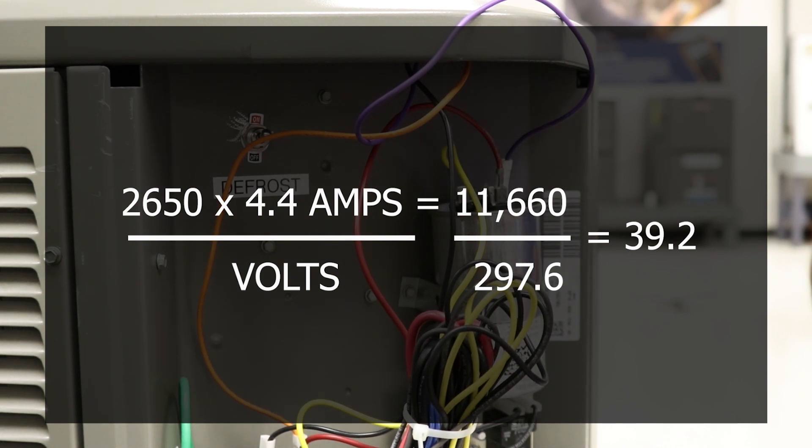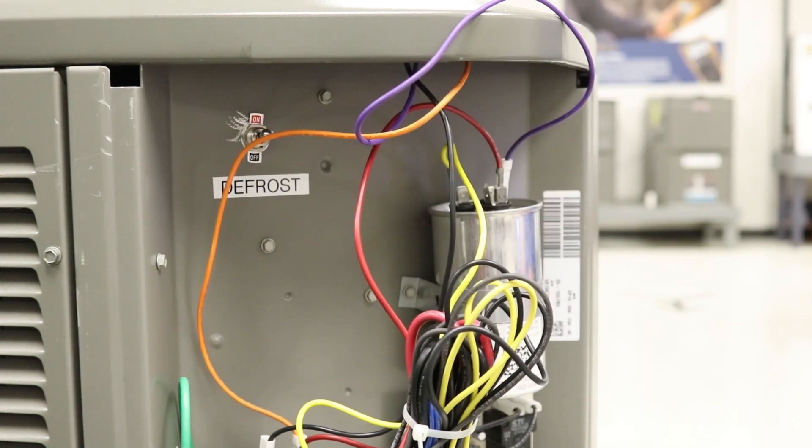Again, this capacitor is a 40 microfarad for the compressor side. So while it's actively running, it's running at 39.2 microfarads. That's the process to check the capacitor itself while it's under load.